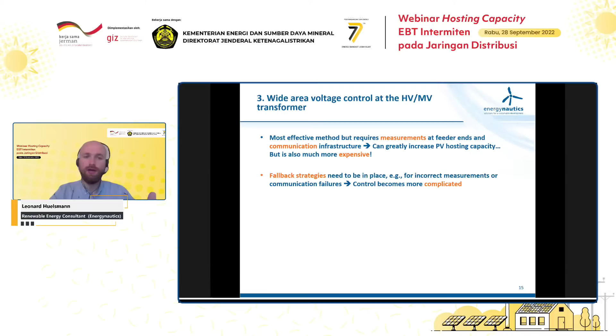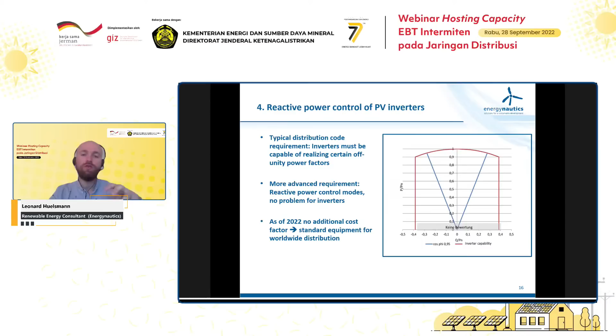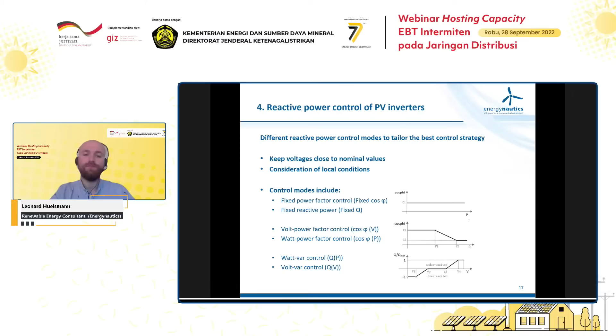What becomes very important is that your PV inverters can contribute to voltage control and improve the situation. This is called reactive power control. Usually this is guided in the distribution grid code: the PV inverter must be able to contribute and consume or generate reactive power. This is again a very technical topic, but it is standard equipment nowadays, and almost all PV inverters have this. The utility could use this feature to improve voltage control, so they should have the knowledge to understand how to use it, how it works and what impact it will have. We still have 5 minutes.